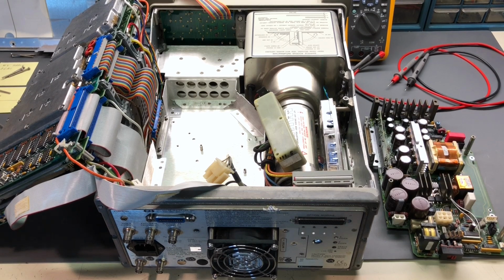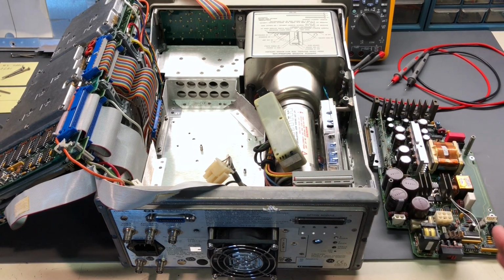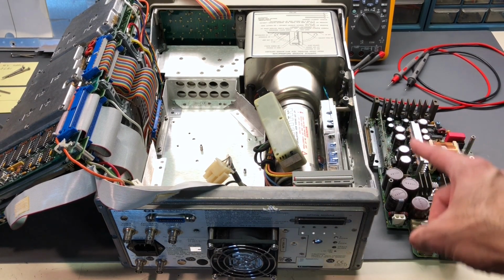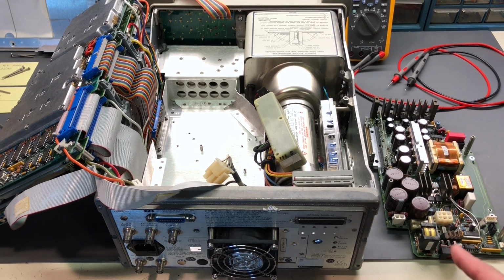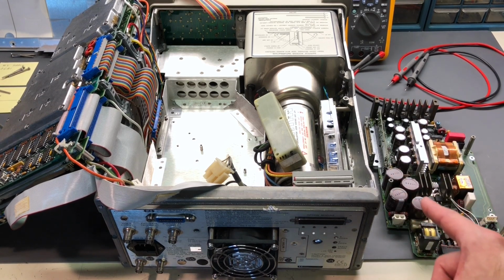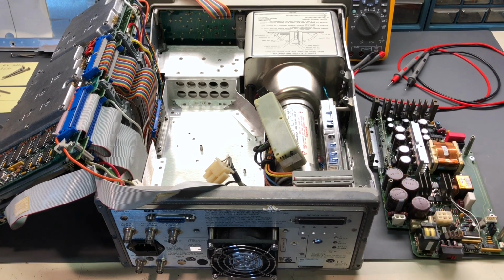But you need to know the correct procedure to discharge that anode before you're working on this area of the spectrum analyzer. There's also a direct AC line connection in this switch mode power supply over here. The AC line comes in this area over here, and these capacitors right here can retain a very dangerous charge. So again, if you're following along, you're doing so at your own risk. So be safe and take care.